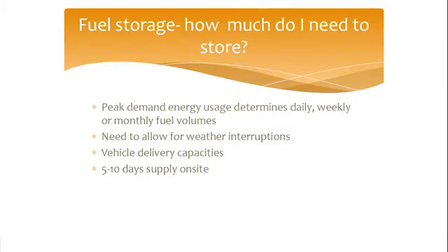Okay, so once we've established what our correct boiler size is, and we've allowed for our heat metering and done the analysis on that, we can then work backwards and think about fuel storage. How much fuel storage do you need on site? Again, as part of your load analysis, that will help you determine how much energy you're using per week, per day, per month.